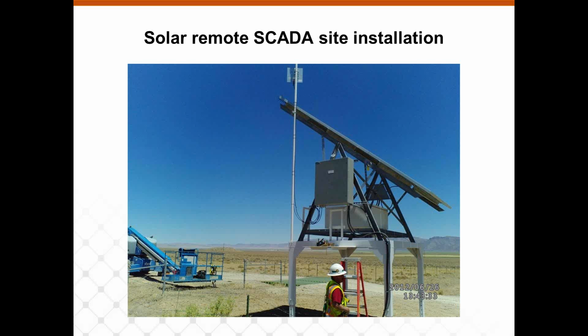We've had no issues except initially, when on-site contractors wired the battery bank for 80 volts instead of 24, which damaged the equipment and burned it out right away — about a $10,000 mistake. Other than that, the system has run for 3 years through summers and winters in the Nevada high desert, and we've been very happy with it.